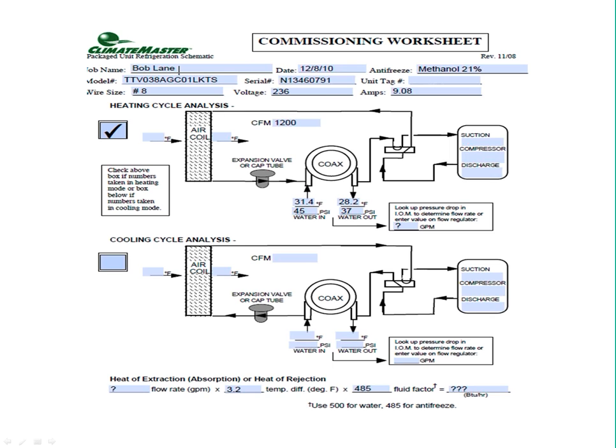So if that's the case, go ahead and disconnect the power to 1 pump, do your analysis to make sure the heat of extraction or heat of rejection, whatever mode you're in, falls within the performance tables of our IOM, and then once you're completed, go ahead and reconnect the power to that pump. But again, that's typically on a glycol loop. So again, folks, I want to really emphasize, I want you to go to the easy fixes first. For example, if you see that CFM is off, you may want to consider going around the house.